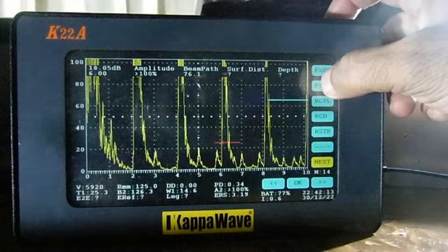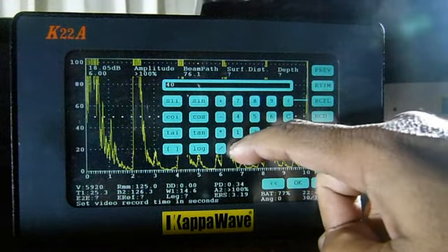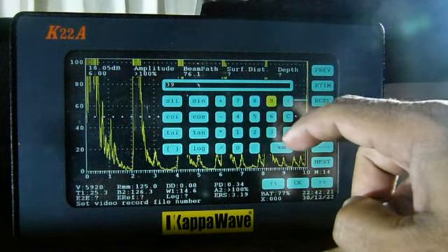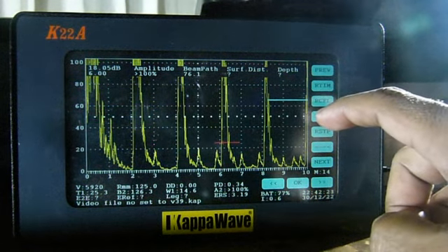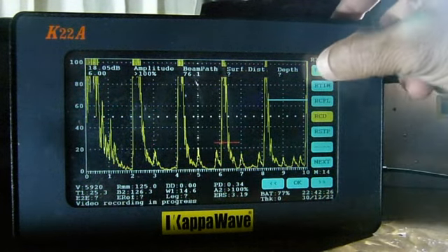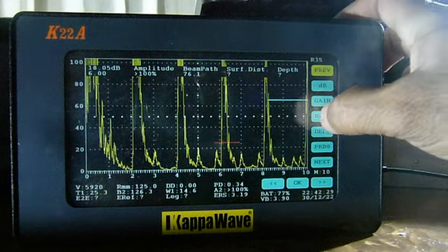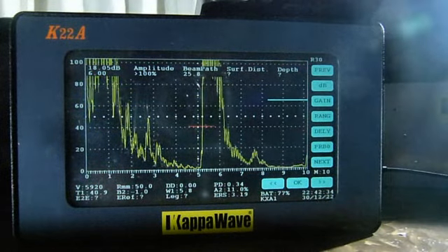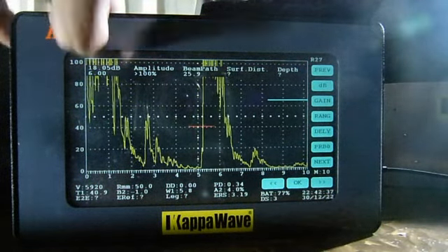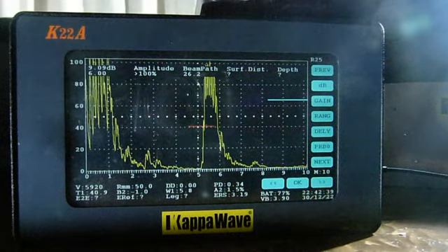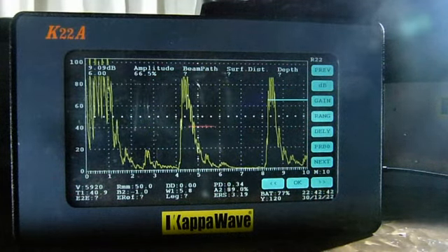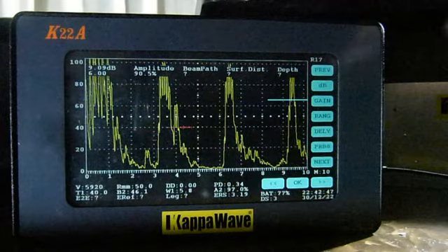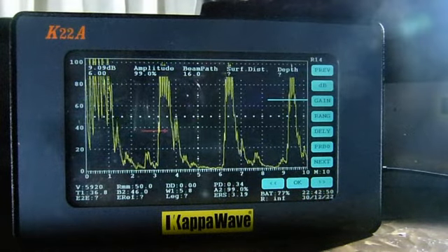In this last exercise, we will provide a 40 seconds time and file number 39, and then we will click record. We will now change the range to 50 mm. We will drag to reduce the amplitude a bit. As I scan other areas, these indications are recorded. I may also move the gate as and when desired on a job.